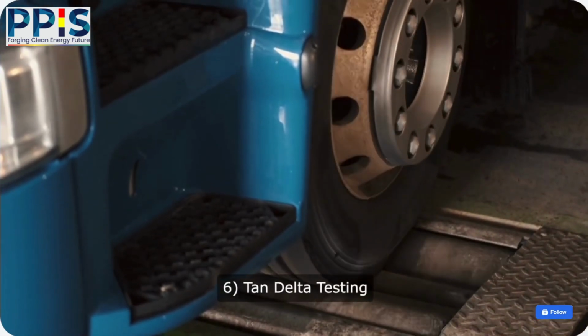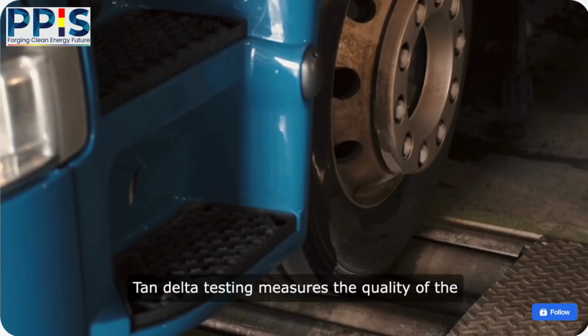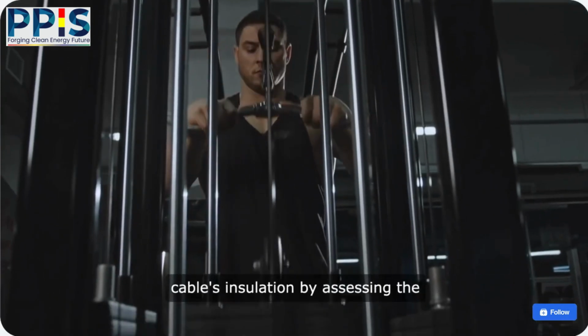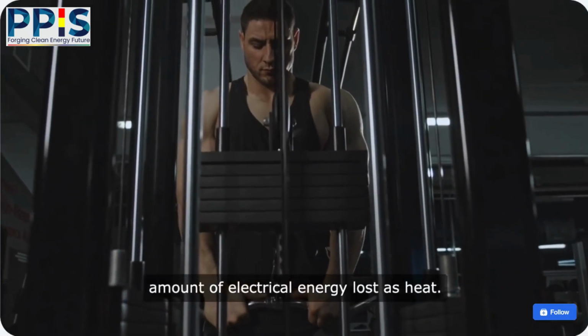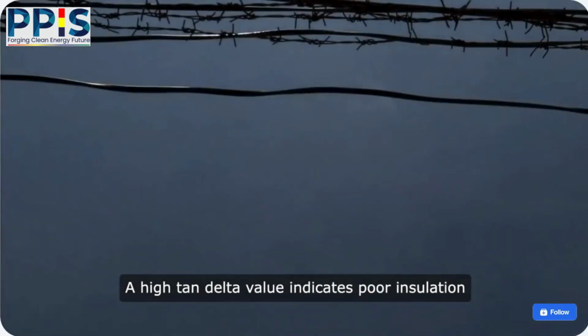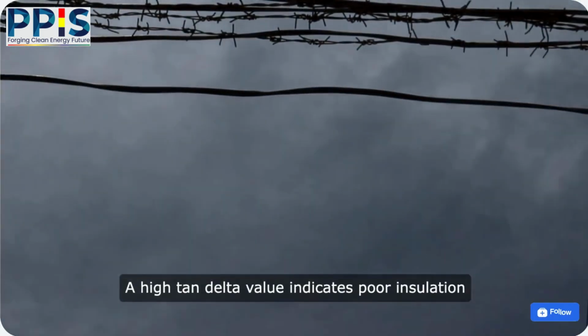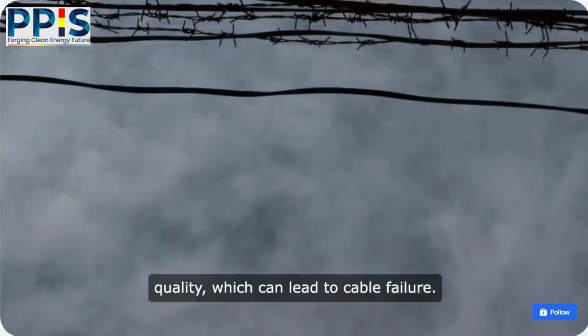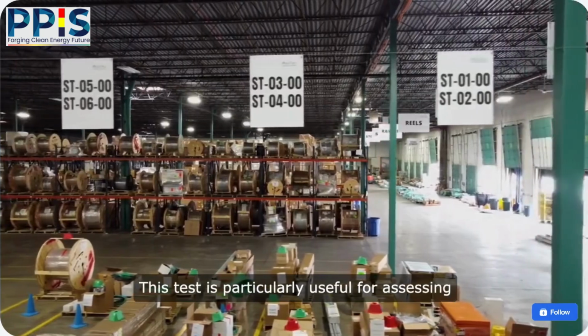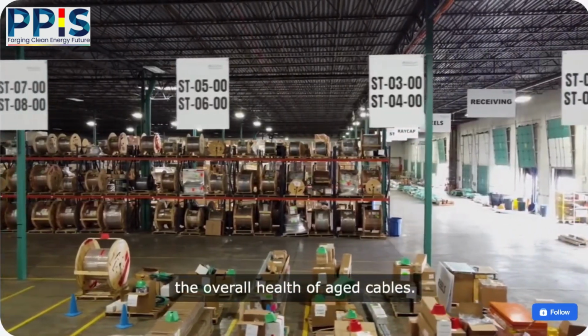6. Tan delta testing. Tan delta testing measures the quality of the cable's insulation by assessing the amount of electrical energy lost as heat. A high tan delta value indicates poor insulation quality, which can lead to cable failure. This test is particularly useful for assessing the overall health of aged cables.